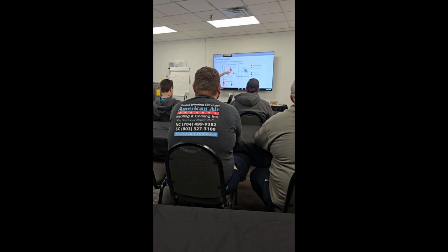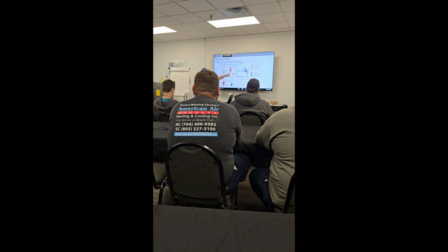Going through my heat exchanger, here I'm looking at what? That's my ambient sensor there. I need to know what the outdoor temperature is so my outdoor fan knows what speed to run. Here goes my coil temperature sensor, so I know what that outdoor coil temperature is.